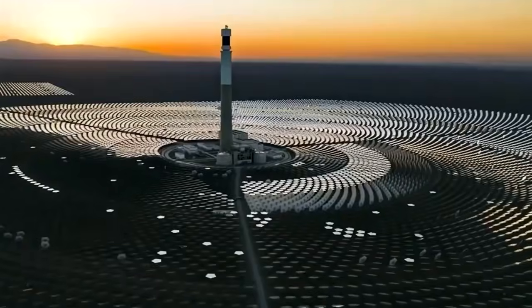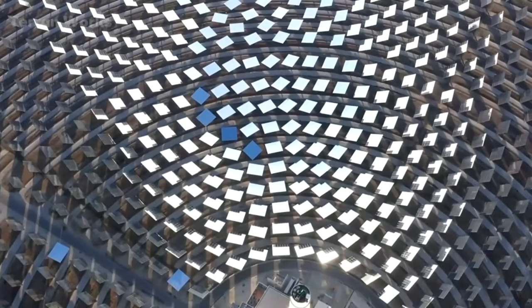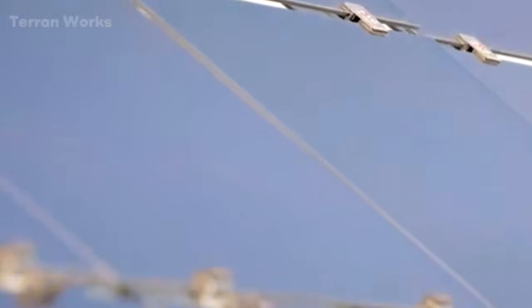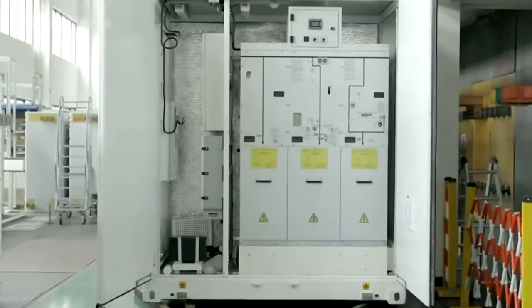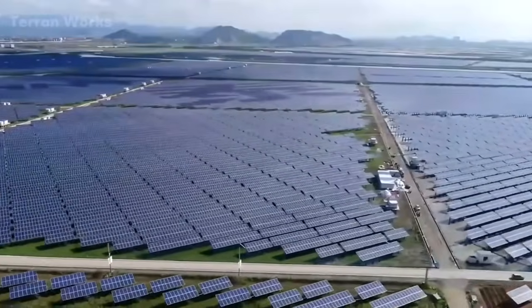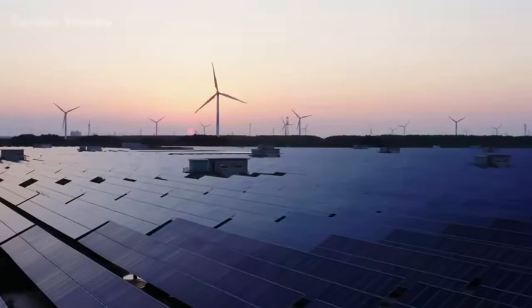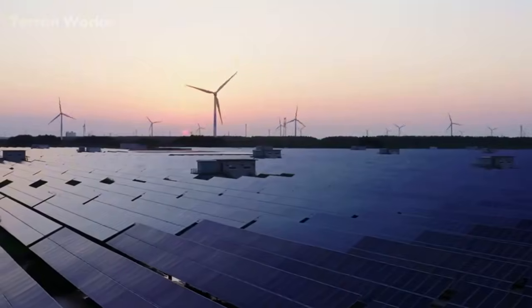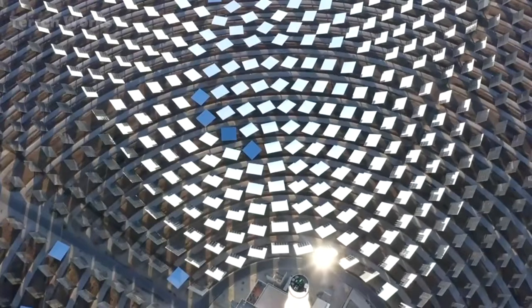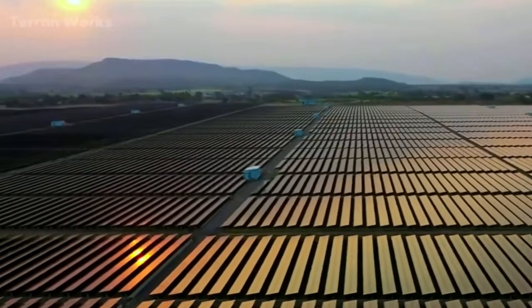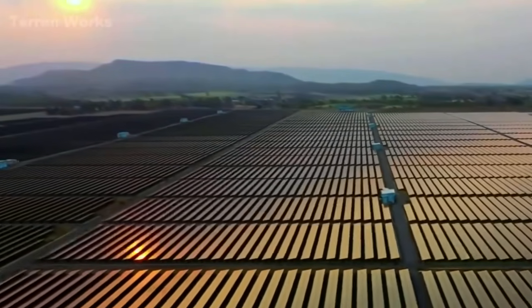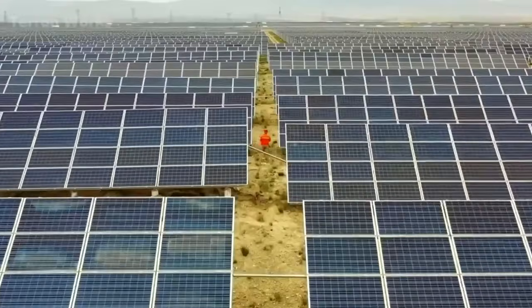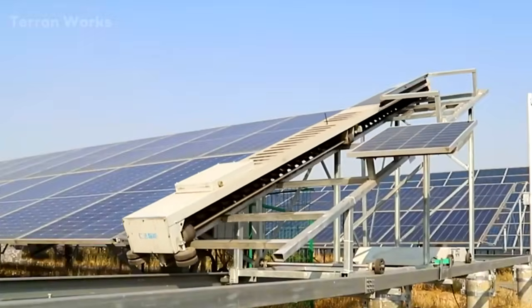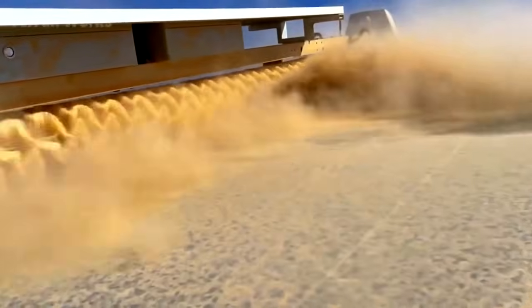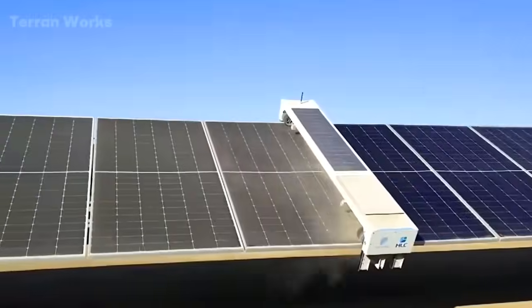Protection equipment watches for faults before export. From there, substation transformers raise voltage to hundreds of kilovolts. Higher voltage lowers current for the same power, reducing heat losses in long conductors. Relay protection and synchronization equipment check the outgoing line before it joins the corridor across several provinces. China's ultra-high voltage lines carry desert power at up to 1,100 kilovolts over more than 3,000 kilometers. Once power leaves the inverter yard and enters the transmission corridor, the weak point moves back to the glass.